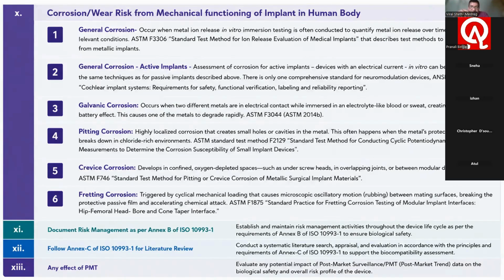Galvanic corrosion generally occurs when two different metals are in electrical contact. It means titanium to SS to chromium. There are different types of metals that are recommended for the manufacturing of implants. So you should also identify the risk of galvanic corrosion. Pitting corrosion is also there. The slides have some information on the standards to be followed depending on the nature of the corrosion. All this information is derived from the FDA guidance documents. They give some ideas on which tests to follow depending on the nature of the corrosion.